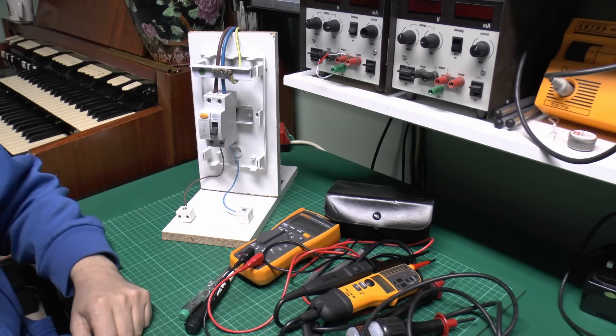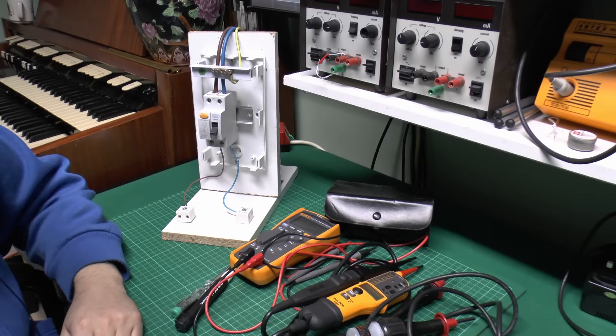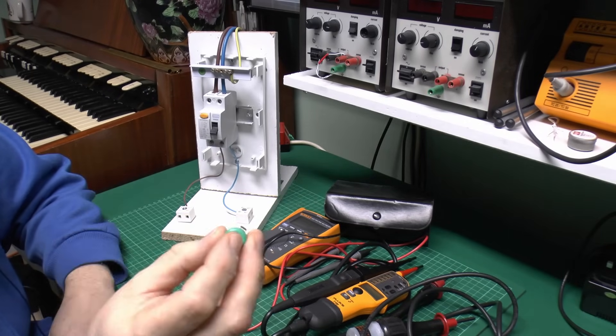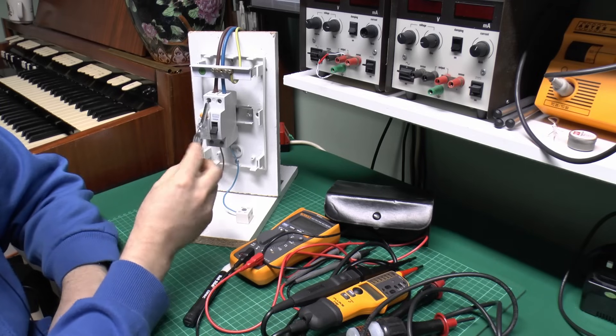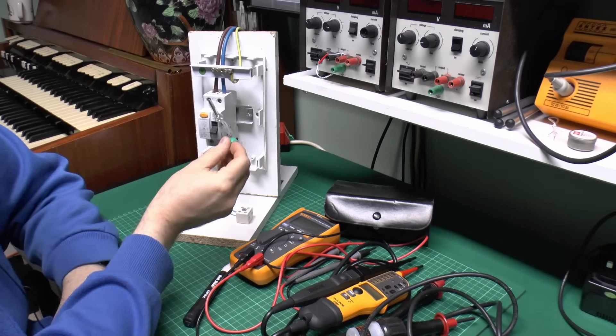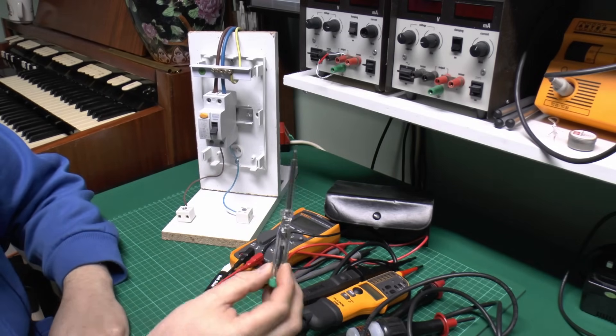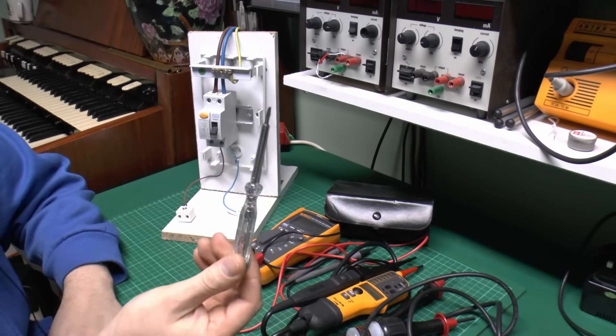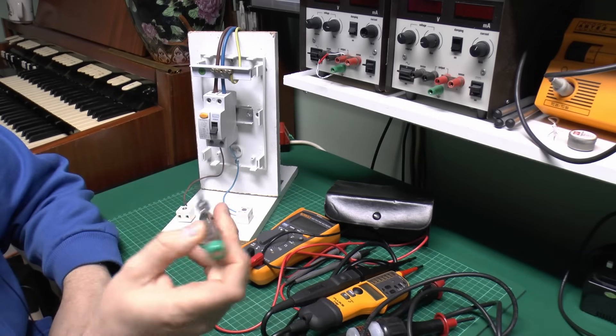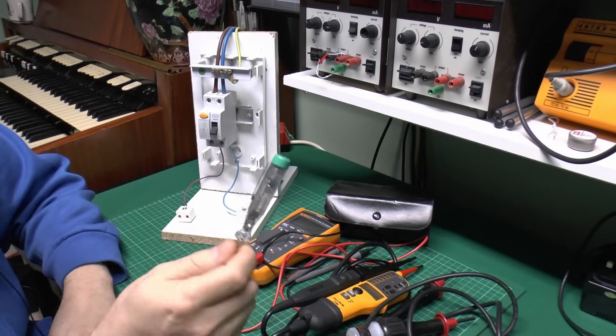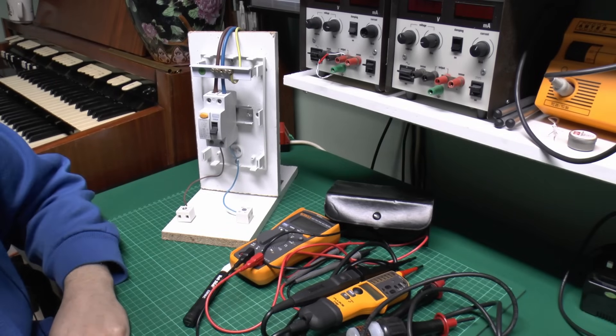And I've got a whole section of stuff here, some of which is appropriate and of course other things which are not. So we'll start with the things which are not, and this of course is first on the list. It's one of those dreadful neon screwdriver affairs where you're supposed to put your finger here on this metal button and then just poke this into the appropriate place, and in theory it's supposed to light up, but it kind of does there but it's so dim, I mean it's really a poor example, certainly not a reliable thing at all. So definitely not going to be using that. These things are unreliable at best and just really dangerous at worst.